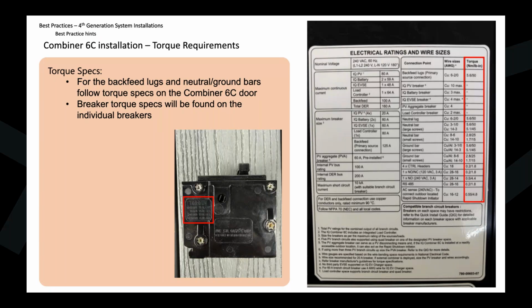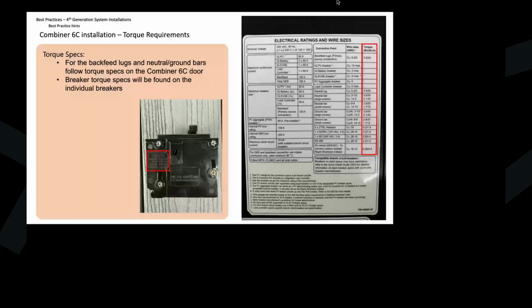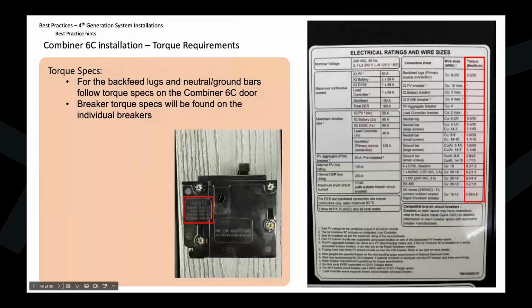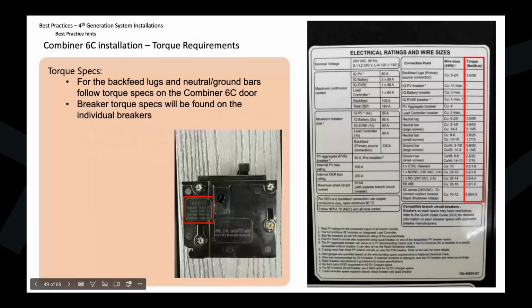Can I say something about that too, guys? I've seen a couple of sites where the main feeder lugs were not torqued down, and a field service tech went out on site and physically had 2 to 3 turns on the main screws for the back feed lugs. Quite frankly, how it shows up is thermal events, like Jarrett mentioned, but we've even seen the system not operating in off-grid mode, just weird stuff.